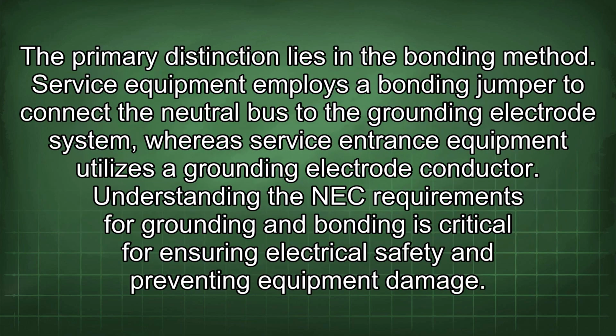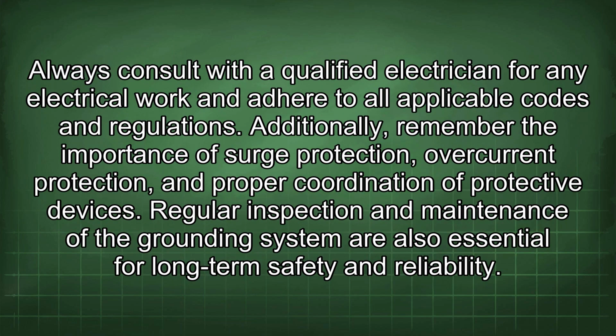The primary distinction lies in the bonding method. Service equipment employs a bonding jumper to connect the neutral bus to the grounding electrode system, whereas service entrance equipment utilizes a grounding electrode conductor. Understanding the NEC requirements for grounding and bonding is critical for ensuring electrical safety and preventing equipment damage. Always consult with a qualified electrician for any electrical work and adhere to all applicable codes and regulations.